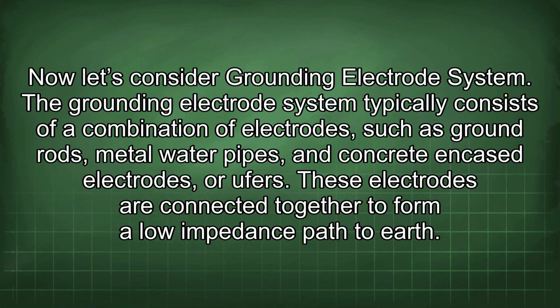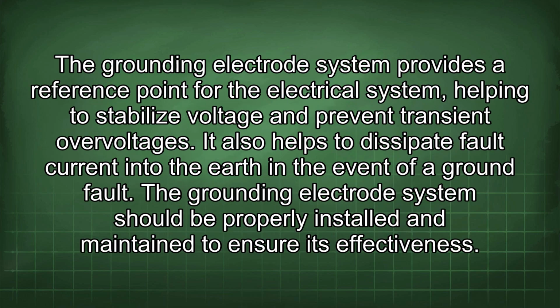Now let's consider the grounding electrode system. The grounding electrode system typically consists of a combination of electrodes, such as ground rods, metal water pipes, and concrete-encased electrodes, or UFERs. These electrodes are connected together to form a low impedance path to earth. The grounding electrode system provides a reference point for the electrical system, helping to stabilize voltage and prevent transient overvoltages. It also helps to dissipate fault current into the earth in the event of a ground fault.